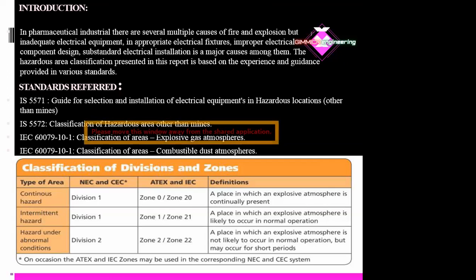Zone 0 is a zone where fumes or chemical particles are present continuously. For example, consider a bottle having some liquid - the inside area of that bottle is considered Zone 0, where the fumes are enclosed in a closed condition in an enclosed area, present 24/7, or to the extent the material is present. Coming to Zone 1, it's the area where fumes are present during the activity or operation.